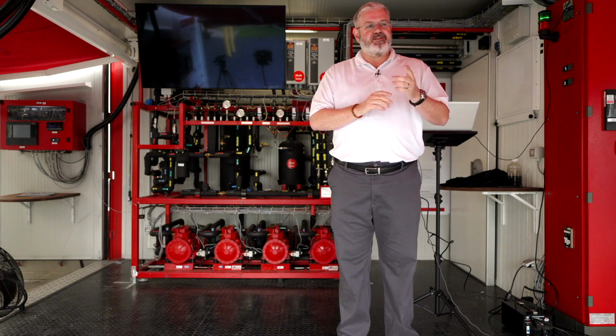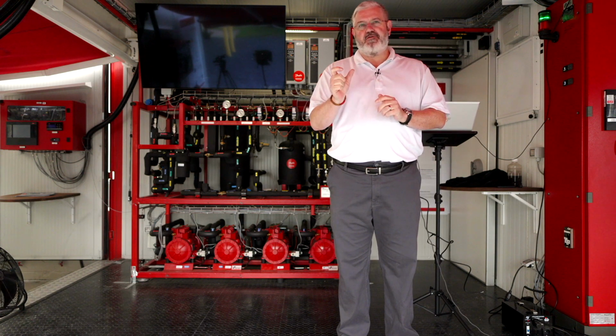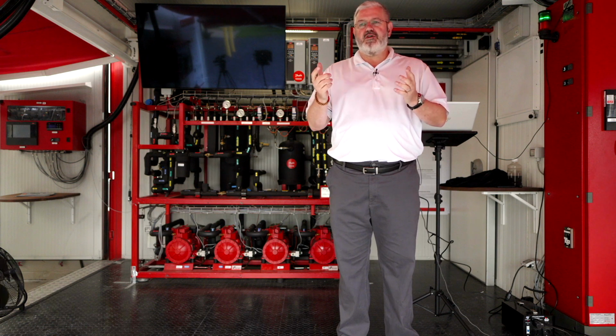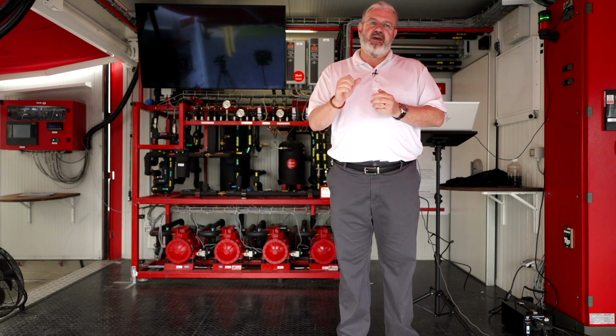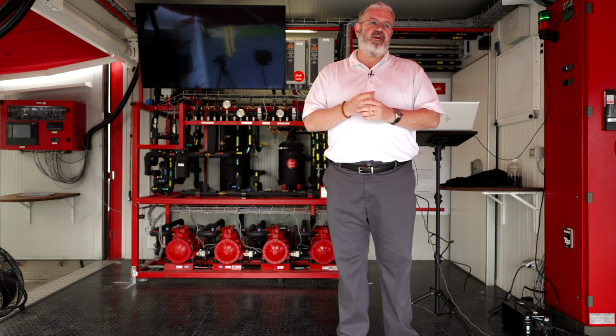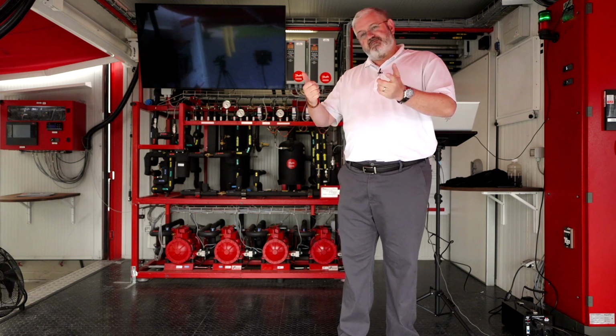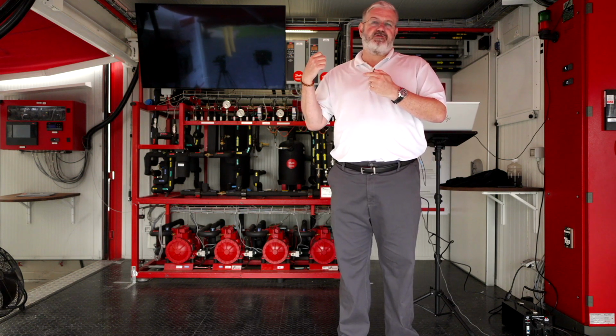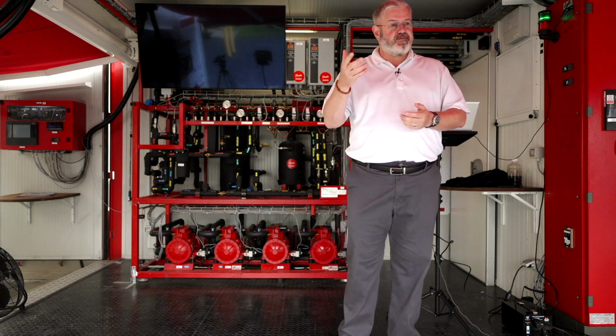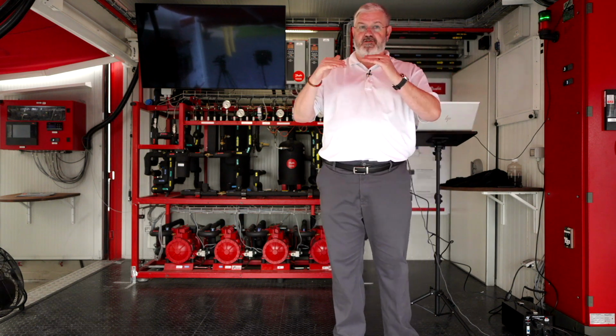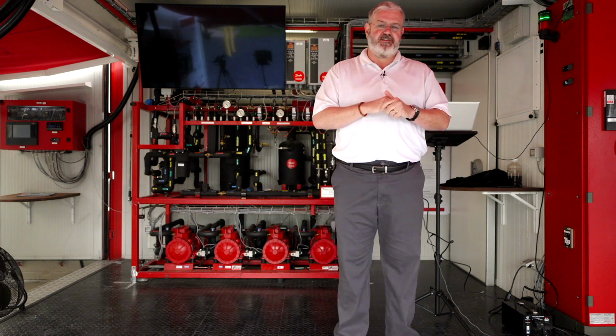But as far as efficiency of the system, CO2 is a much better refrigerant. It just does more work. That's why you have smaller line sizes on the liquid. It doesn't take as much to do the same amount of work. However, there's a trade-off. The components are more robust. They cost more to build, so they cost more to buy. So there is absolutely an initial cost increase for a CO2 system versus an HFC.